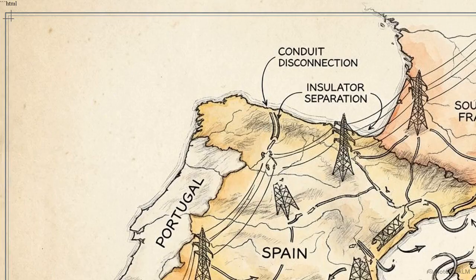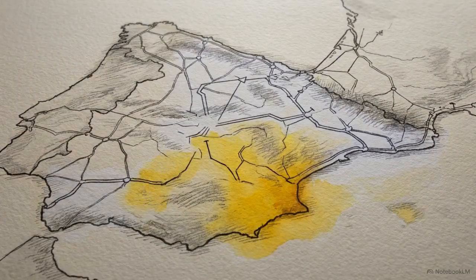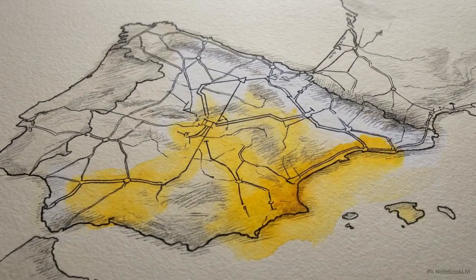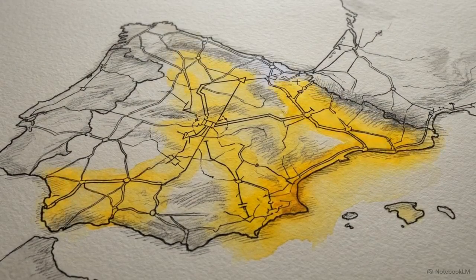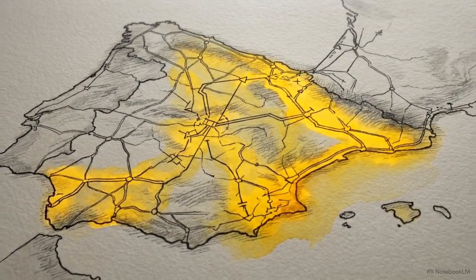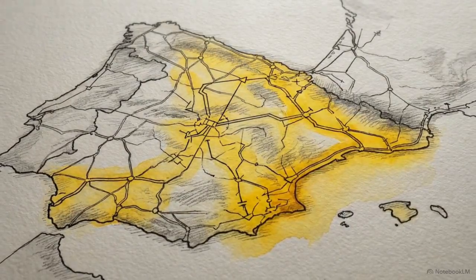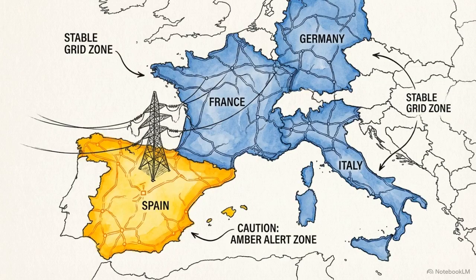To damp these oscillations, grid dispatchers took manual operational measures. They reduced power exports to France and coupled internal transmission lines in the south of Spain. These mitigations worked, but created a critical physical consequence. Altering the transmission topology inherently increased the baseline voltage across the entire Iberian power system. The Spanish 400 kilovolt transmission grid operates under standards that allow for a wider voltage range than neighboring European countries. This makes it uniquely vulnerable when voltage climbs.